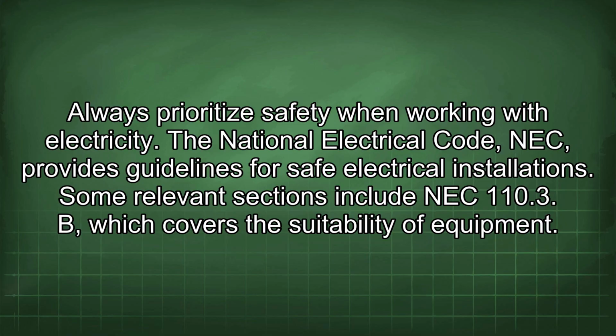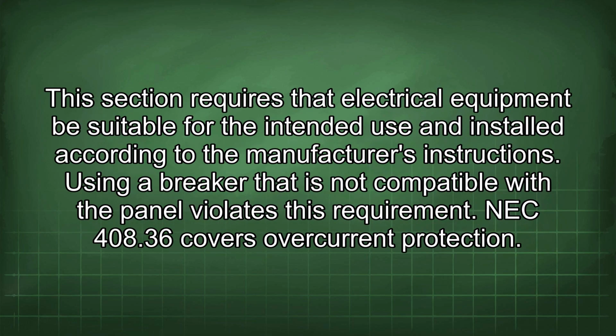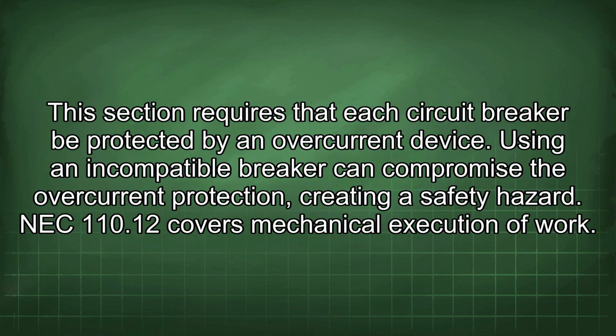Some relevant sections include NEC 110.3(B), which covers the suitability of equipment. This section requires that electrical equipment be suitable for the intended use and installed according to the manufacturer's instructions. Using a breaker that is not compatible with the panel violates this requirement. NEC 408.36 covers overcurrent protection. This section requires that each circuit breaker be protected by an overcurrent device. Using an incompatible breaker can compromise the overcurrent protection, creating a safety hazard.